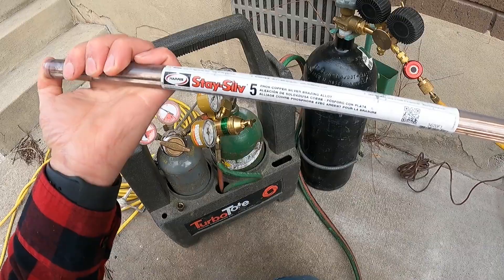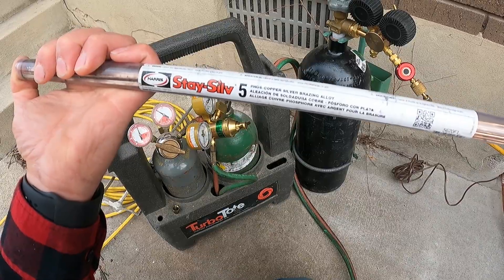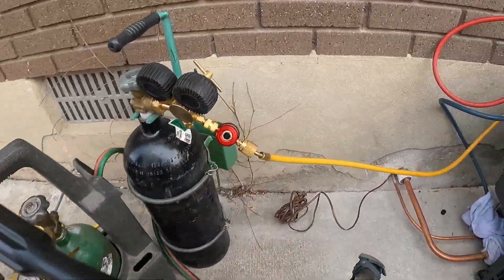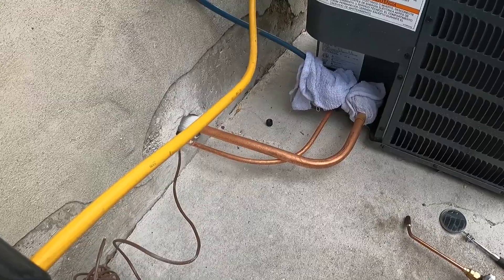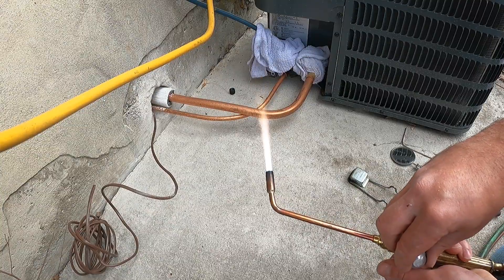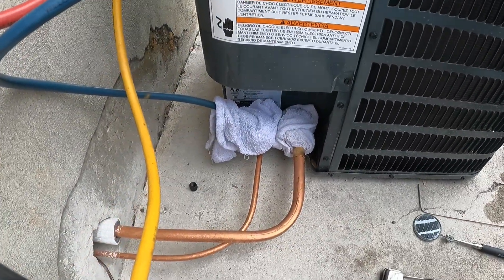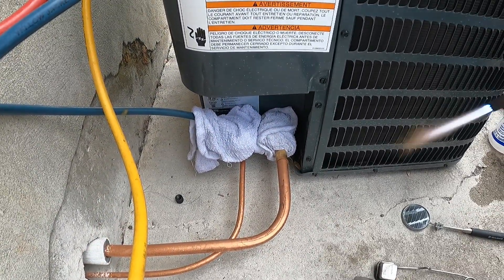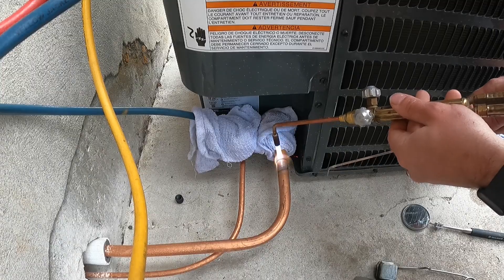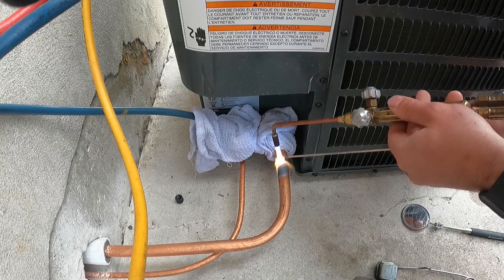Our Sil-Fos — many people call it different things, but what I use is called Stay Silv 5, a copper-silver brazing alloy. It has a certain percentage of silver in the rod, which makes it extremely easy to braze with. Notice how quickly I can get to the point of adding my Sil-Fos — it heats up that fast.